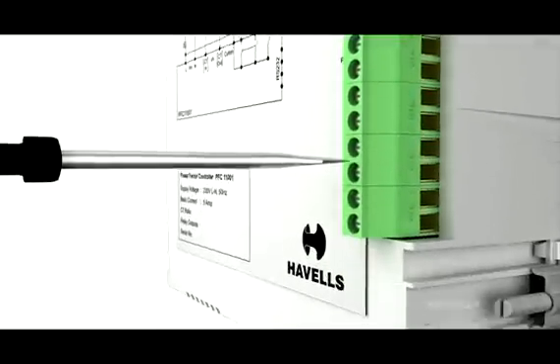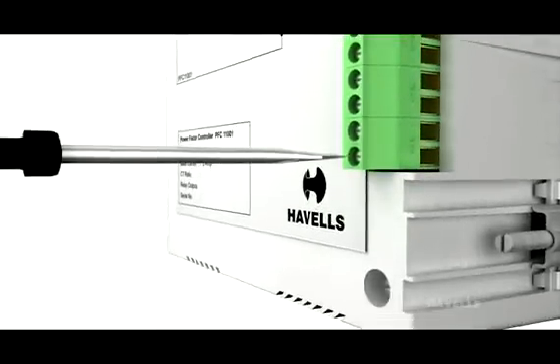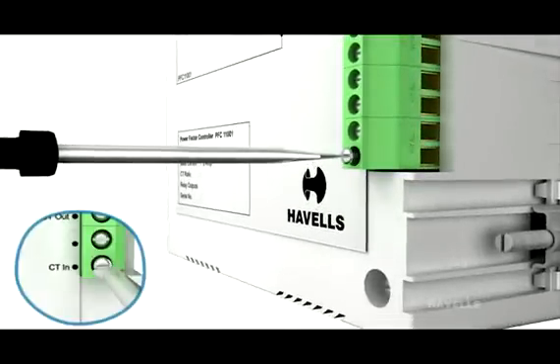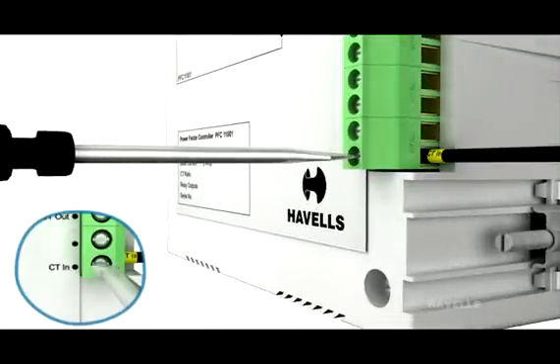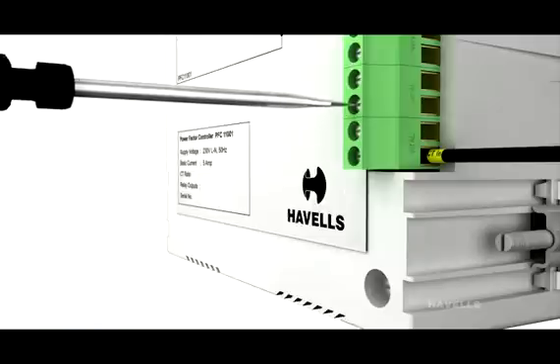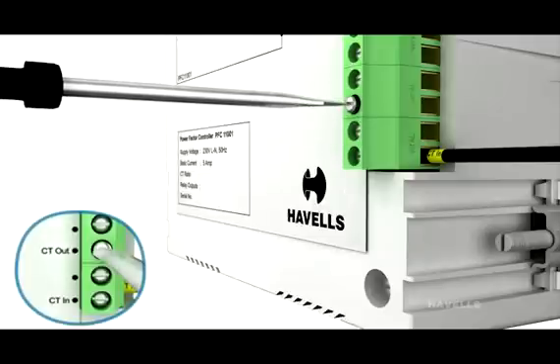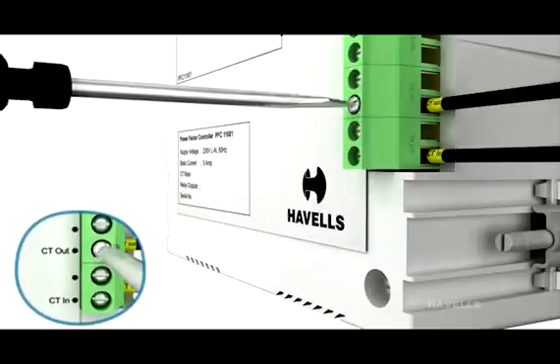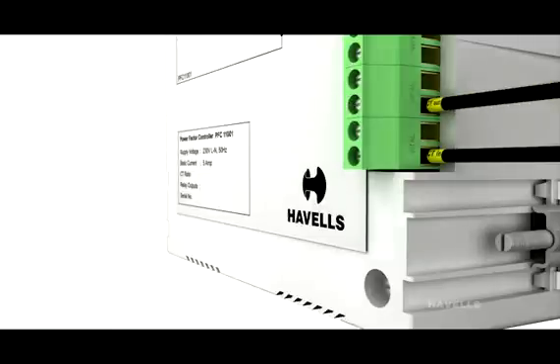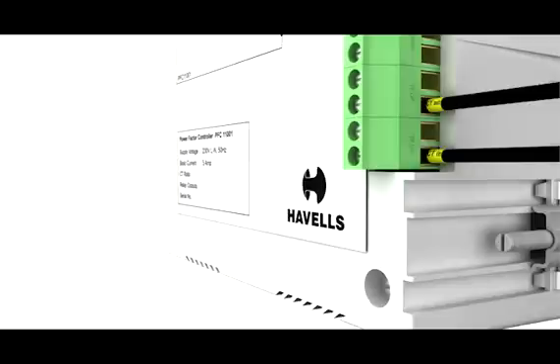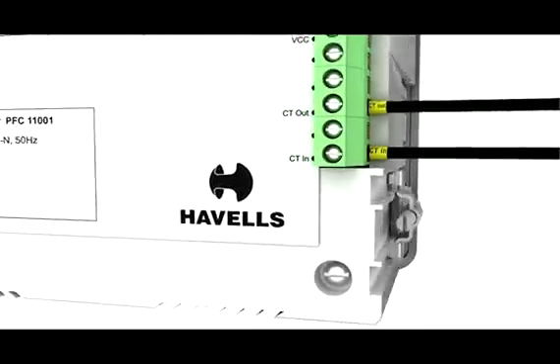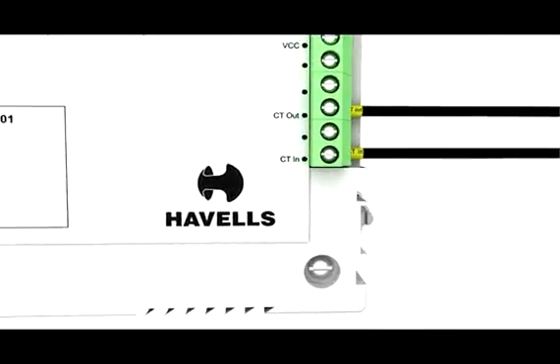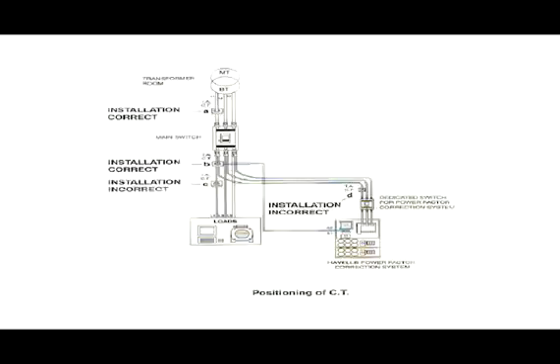Then connect CT's input to the CT in terminal of connector and CT's output to the CT out terminal of connector. Note that here, the CT should be placed in the same phase through which you have taken the phase voltage and choose CT as per the load.